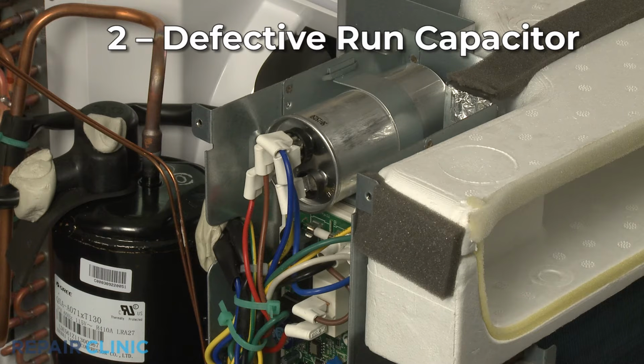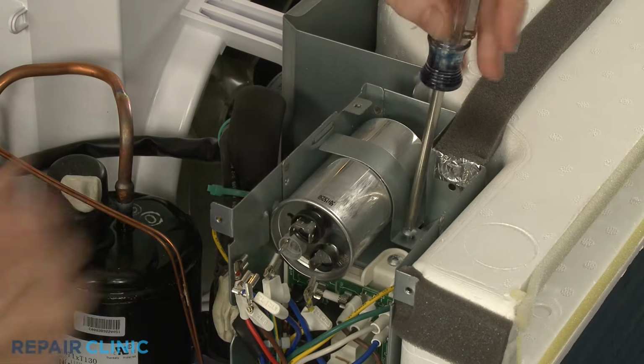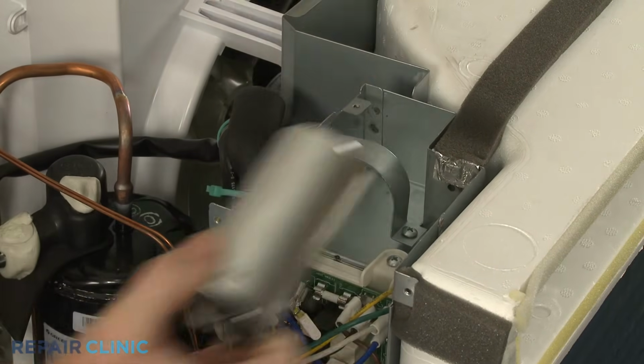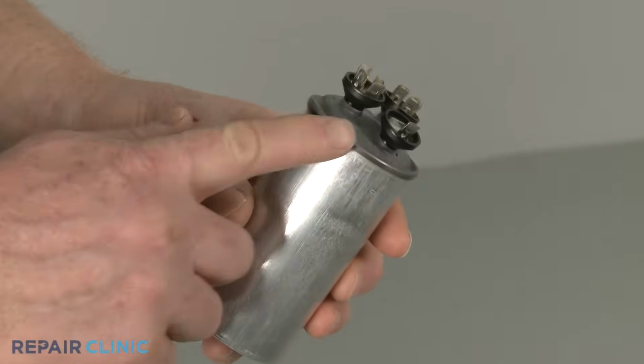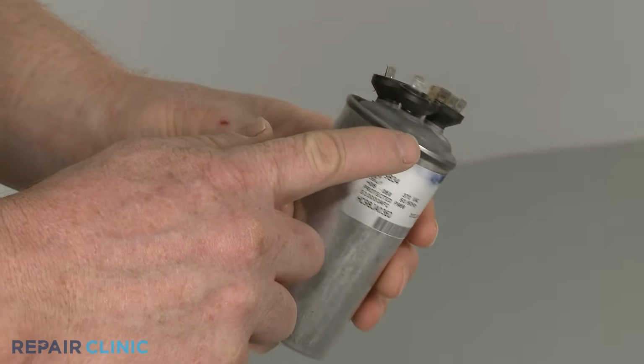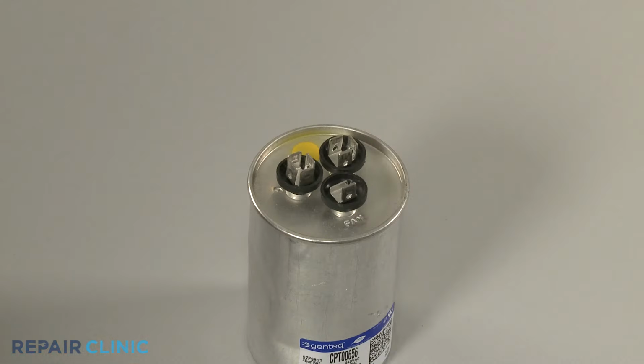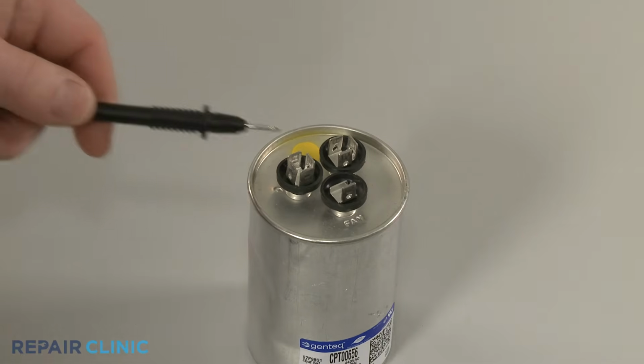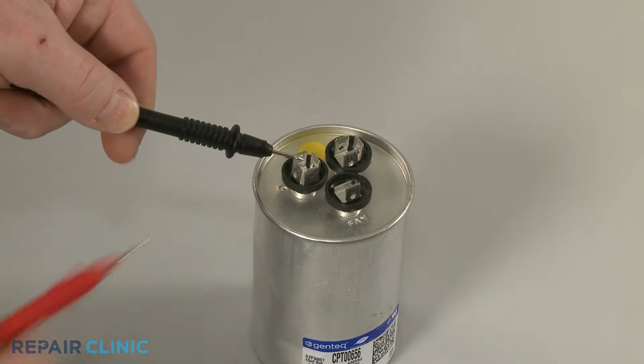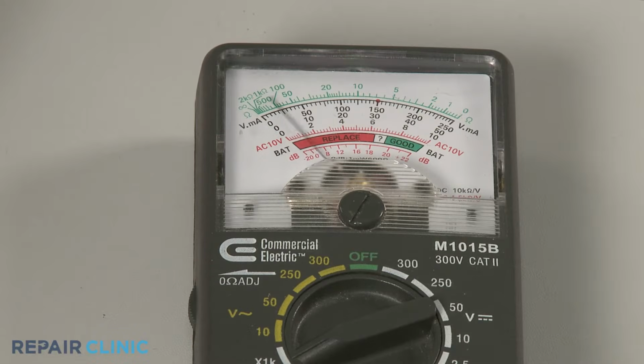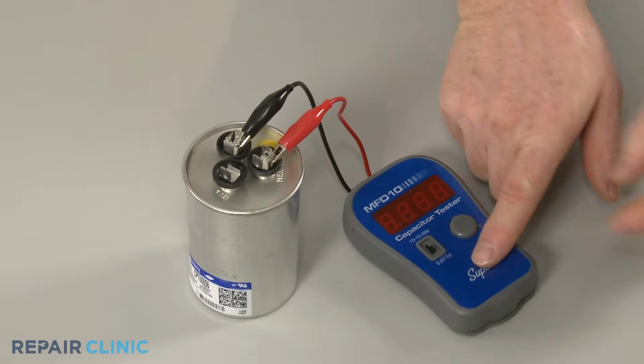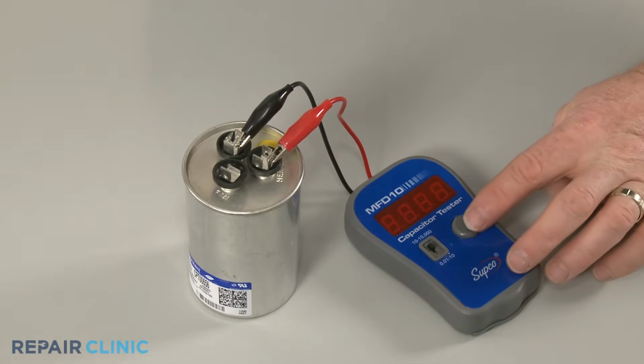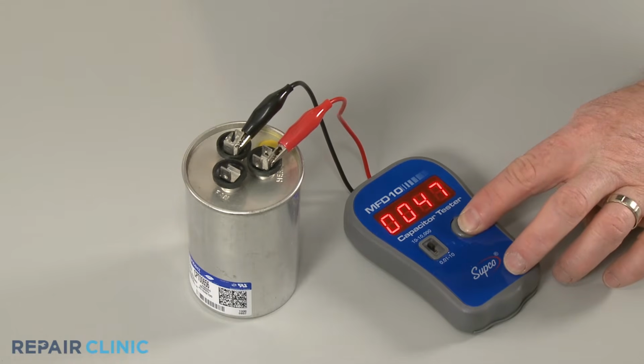A run capacitor stores an electrical charge, then releases it to power the compressor. If the capacitor is defective, the compressor won't run. When a capacitor fails, it will often bulge or leak. You can also determine if a capacitor is faulty by using a multimeter to test the capacitor's ability to store and release an electrical charge, as well as determine if the component has a proper capacitance rating, provided the multimeter has a capacitor testing function.